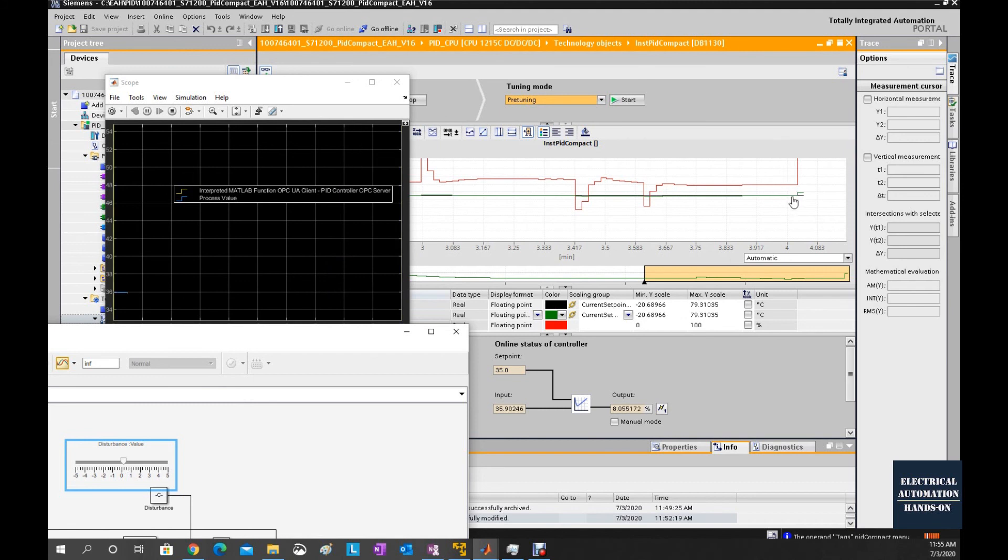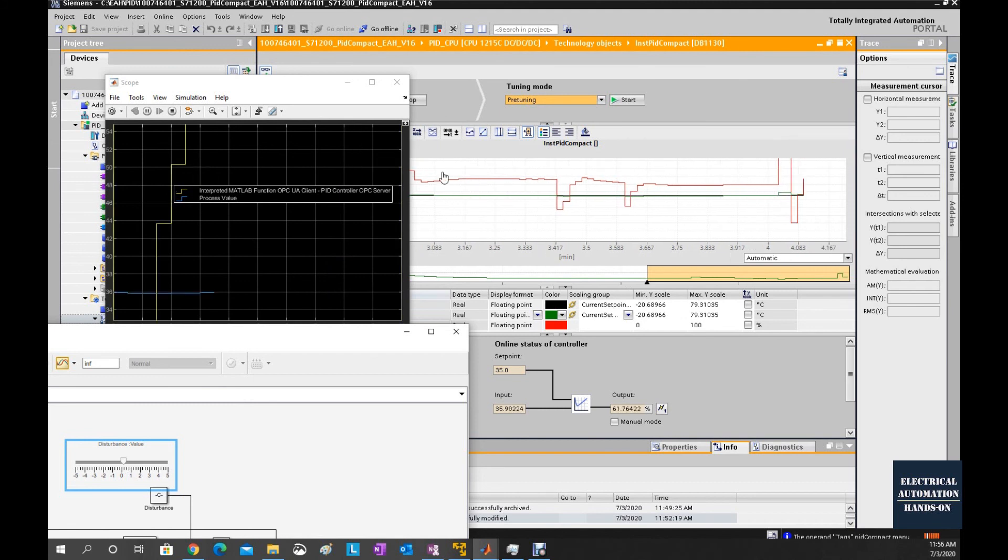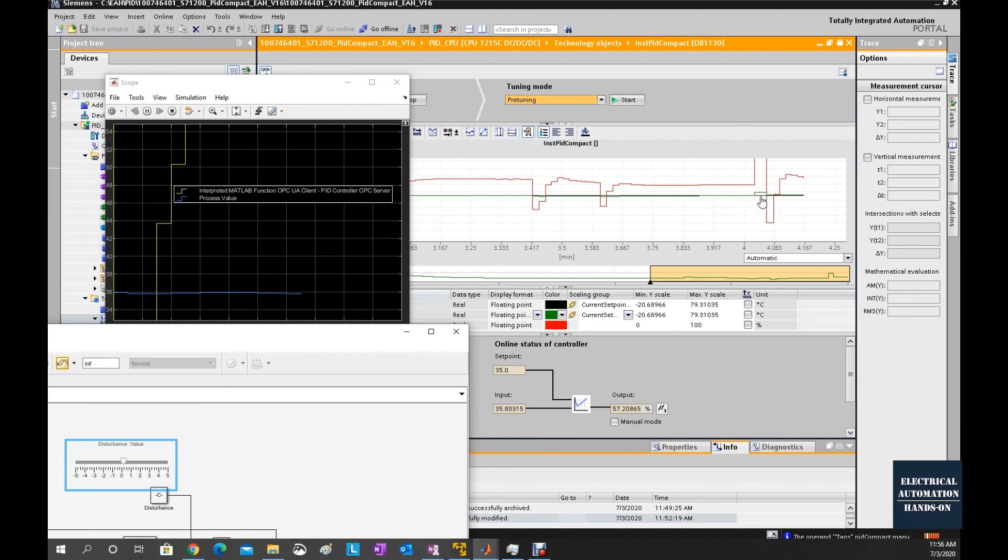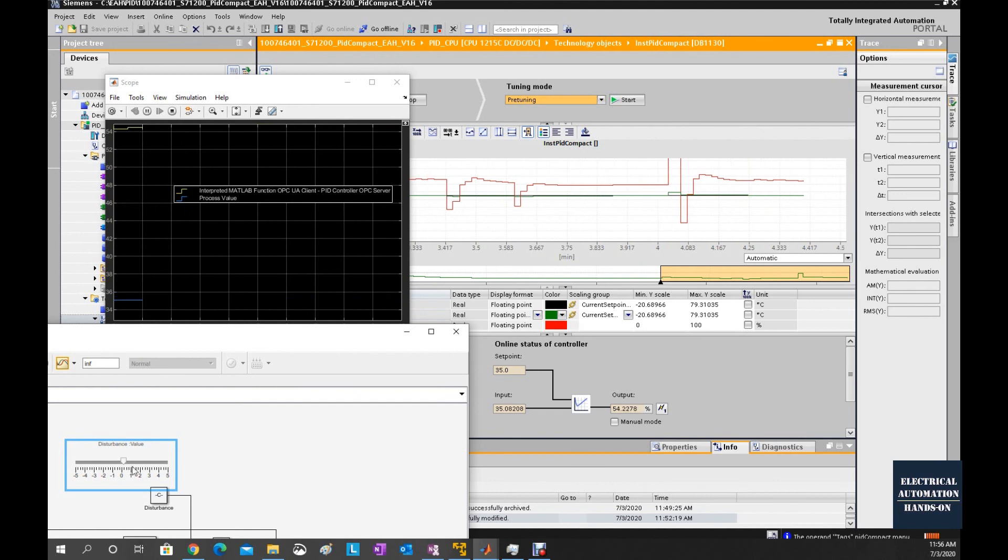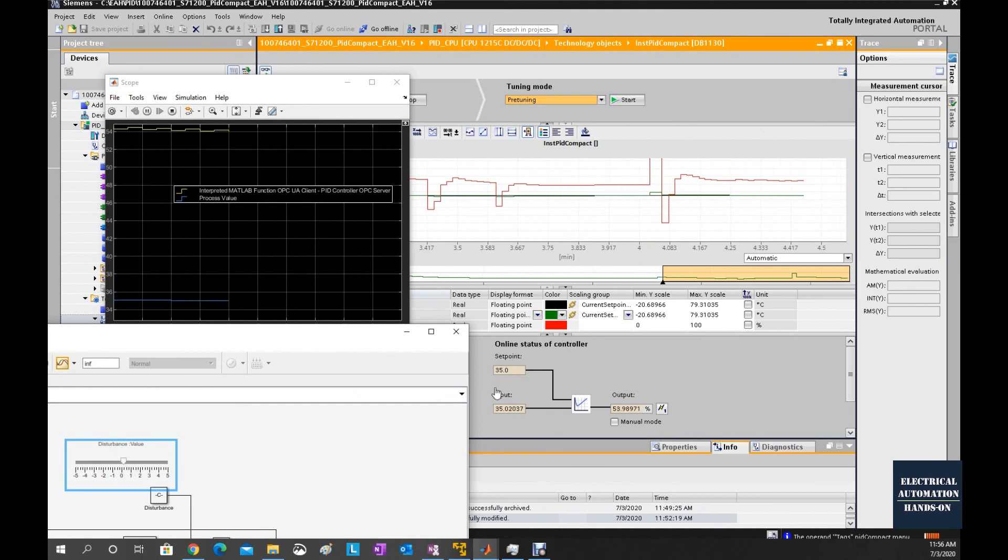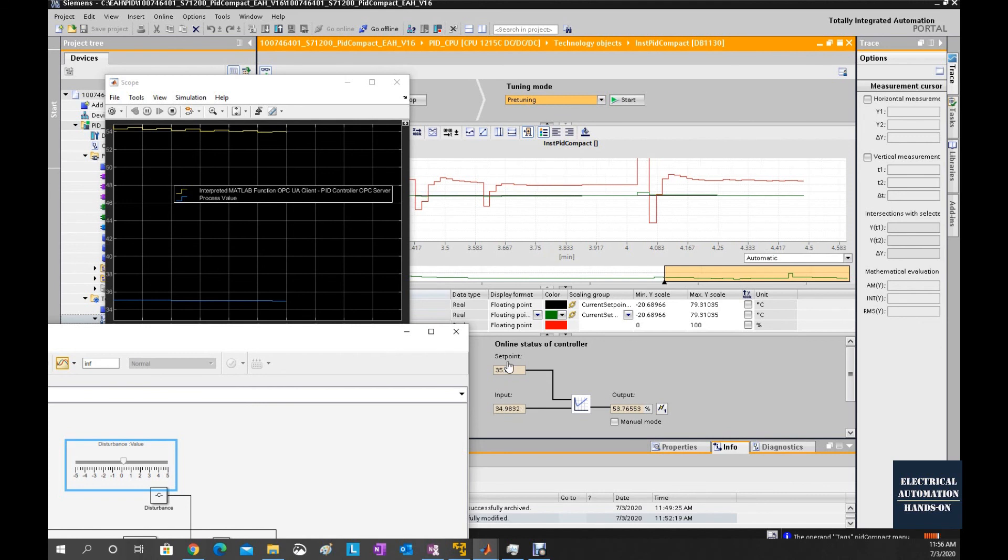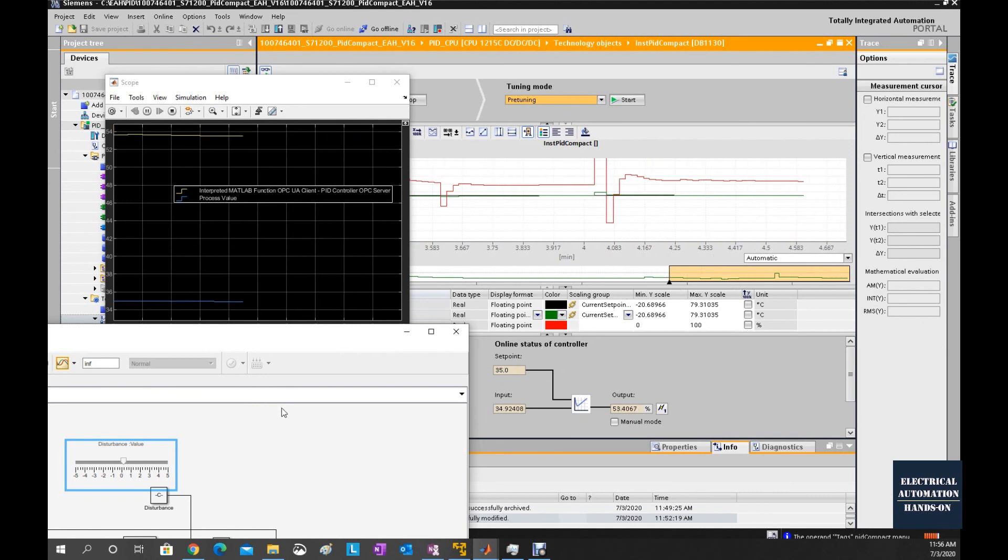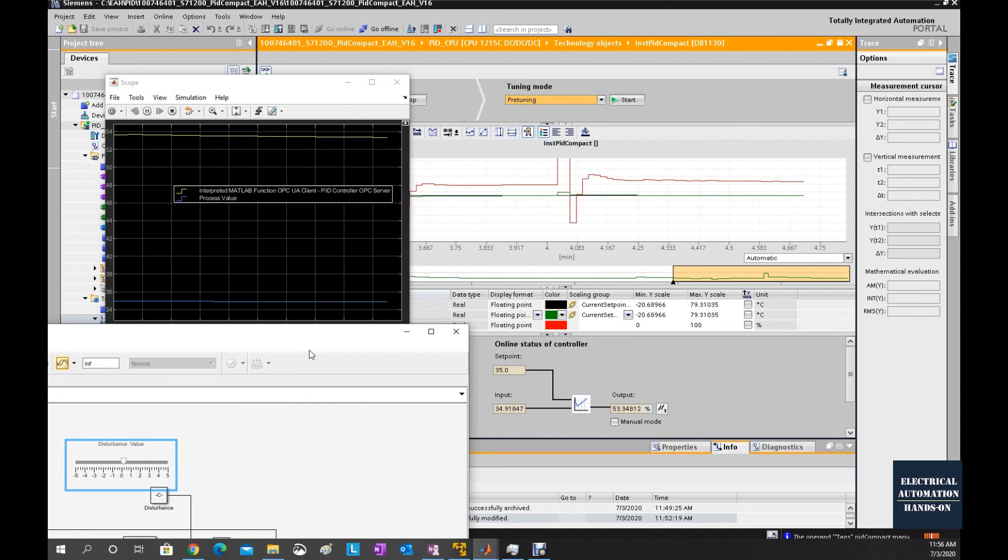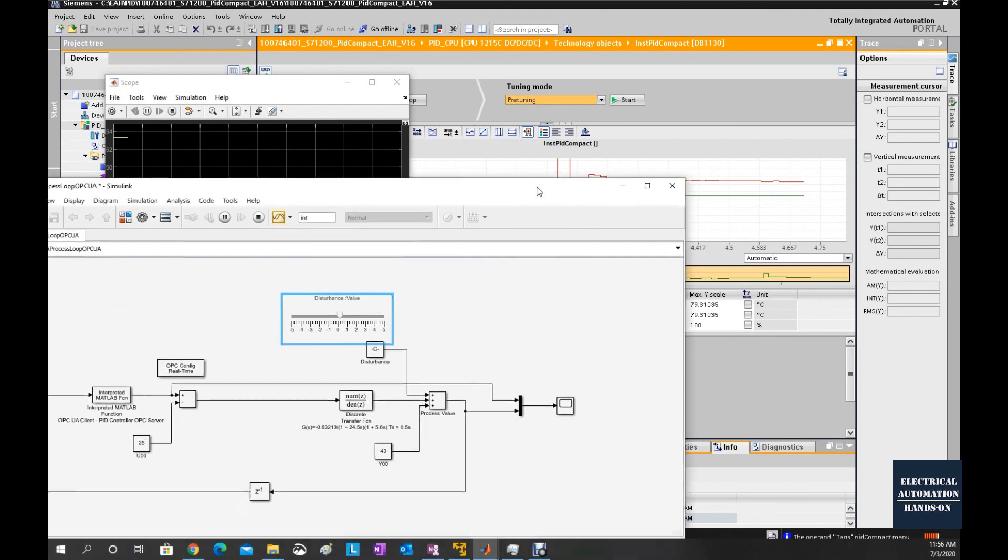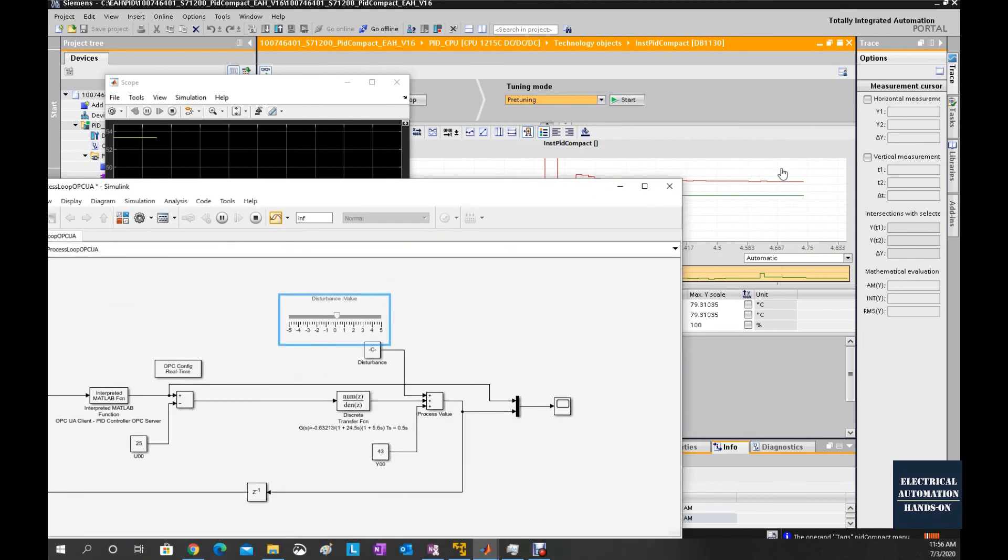We will see this change from the scope and from this curve. Even if I give the disturbance, the process value is still working around the setpoint. That means this PID is working. The communication between the MATLAB Simulink simulated process loop and the PID from our PLC, they are all working properly.